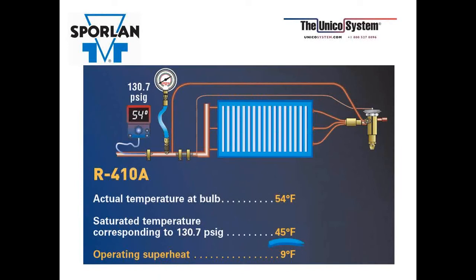Since the TEV only controls superheat, it is very important that you understand how to take a good superheat reading. Use your temperature probe to take a good temperature reading. Use your manifold gauge to get a good pressure reading. Then use your PT chart or the Sporlan Chillmaster PT app on your smartphone to convert this pressure to a temperature. You find the difference between the two, and that's your superheat. In this case, we're looking at 54 degrees at the bulb, and this 130.7 psi, converted to temperature, would be 45 degrees, so you have a difference of 9 degrees, so that's your operating superheat.